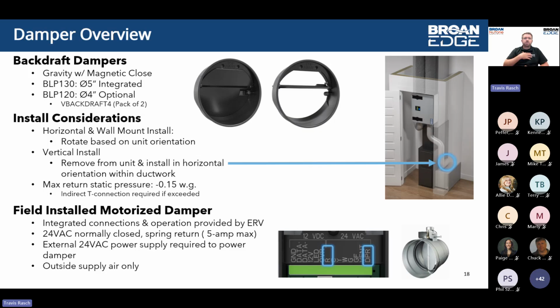It's not something that we at Broan offer in this type of configuration, but the product has integrated connections to do it. If you hook up the contact closing of that motorized damper to both the R as well as the DPR connection on our Broan Edge product, the Broan Edge will dictate when that field-installed motorized damper opens and closes. The Edge will not provide the power required for that motorized damper to operate.